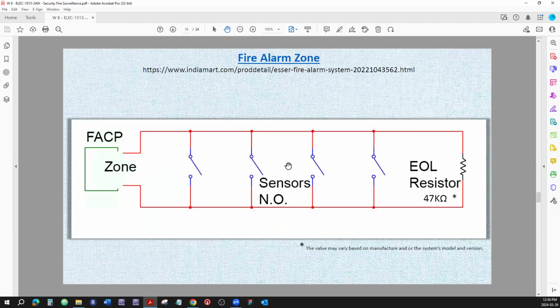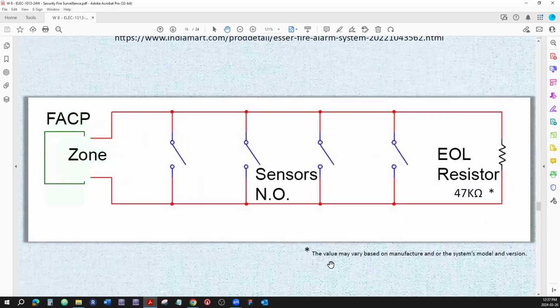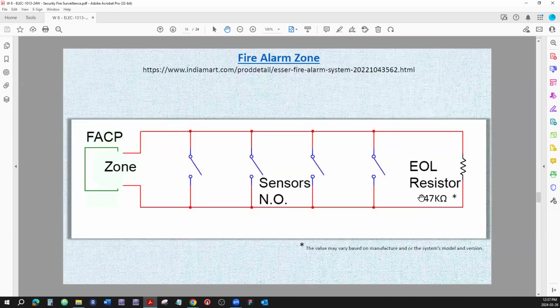Forget these exist. What this zone sees is that end-of-line resistor, and that end-of-line resistor should be at the end of the line, behind the last sensor. Usually it's 47 kilo ohms, but depending on the make and model of the fire panel, the values may vary, so it has to be whatever that specific panel requires, usually 47 kilo ohms. So what happens? The fire alarm zone looks at what it reads, it sees 47 kilo ohms, and everything is good.